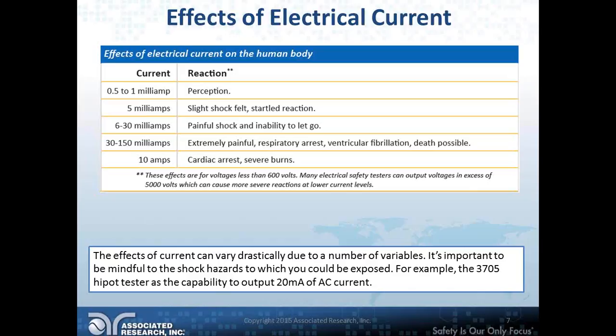Again, the instrument itself would most likely shut off were you to run into a case like this, because you do have some runaway current. But at the same time, consider it from the standpoint that this is going to be very unpleasant if I come into contact with live energized voltage while using this equipment. So something to be very aware of.